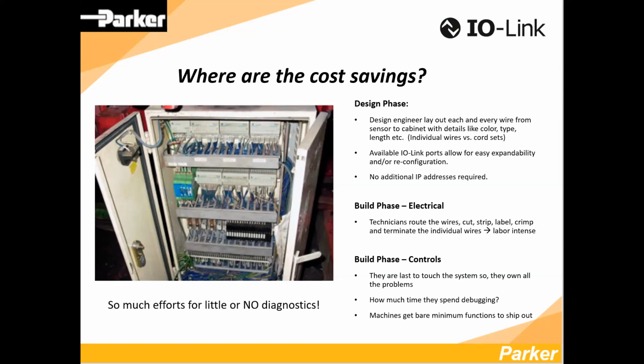So now it's basically 4 or 5 to 1. And as far as templating IO-Link, it's actually a lot easier to template than custom hardwired drawings. In the build phase, when you're putting this together, you're deploying and commissioning this hardware instead of routing and landing individual conductors or multi-conductor cables through panels to terminal strips—it's just connecting connectors. That leads right into the buy-off and the automation or running portion. As far as debugging, if you're just connecting a cable as opposed to landing individual conductors, your debug time is going to be cut down significantly.